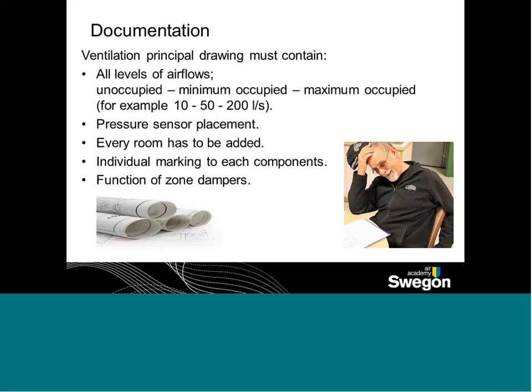Something which maybe seems boring but needs to be considered: whenever you do any sort of system, particularly DCV systems, everything must be documented properly. The levels of airflow — unoccupied, minimum, maximum — where you're putting the pressure sensors, what sort of flexibility you want in the room in the future, what rooms should be added. You need to make sure that each component is marked up and what its functionality is. Very easy to get missed.